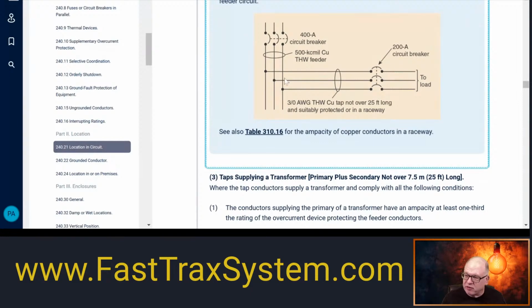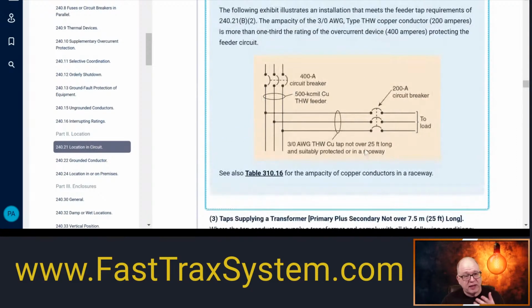These applications mean that you get screwed, because you were utilizing the tap rules for a reason, right? And so now these conductors are protected at what? These conductors are protected at 400 amps. These conductors right here are no longer taps anymore. And you just happen to be feeding a 200 amp overcurrent protected device. So you're going to be limiting the load on those conductors, which could already be rated for 380 amps. You just, one, have to make sure the lugs are okay. But in doing that, then you don't have a feeder tap. You don't have feeder rules because everything is the same size.